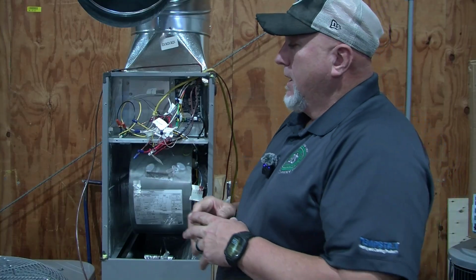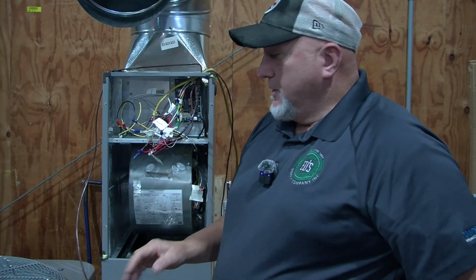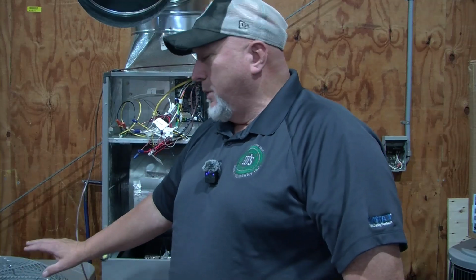Now you see our timer went out and our condenser unit kicked on, so it's back in AC mode. Now, you can hear how quiet it is. These units are made to be that quiet. If you hear louder noises, or you hear strain, or you hear any kind of rattling, rattling's not normal. There were some compressors that, when it shut off, would make a rattling sound, and that was because Copeland took the check-off valve or check valve out of the top of the compressors, and I think they went back and cured that on these new ones.